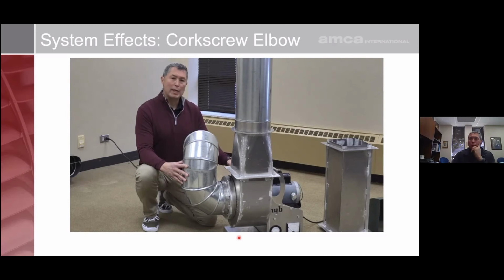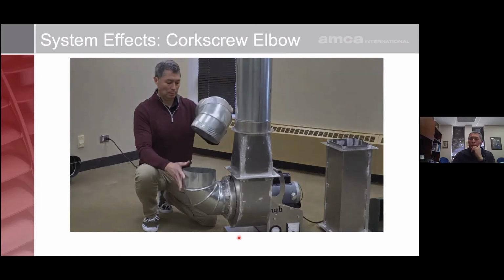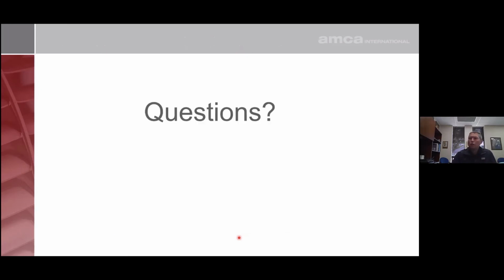So if we were actually able to take an amp reading and do an efficiency calc, even though this fan's producing more pressure, it's doing it much less efficiently. Horsepower has actually gone up, and that's kind of evident in the amount of noise that the fan's producing. Any questions on corkscrews before we move on to inlet boxes?